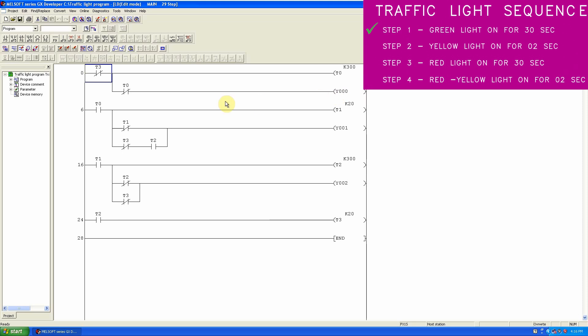In the next rung, we use the normal open contact of T0 to start timer T1 for two seconds. The normal close contact of timer T1 will turn on the yellow light Y1 for two seconds. This is the programming for step two.